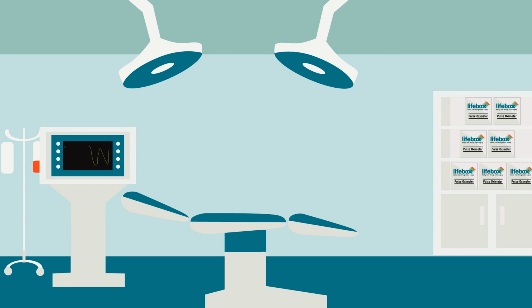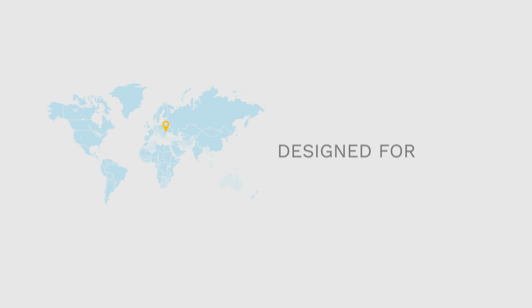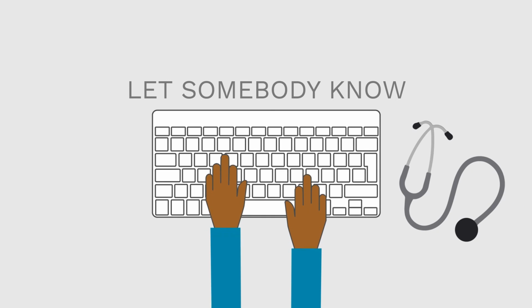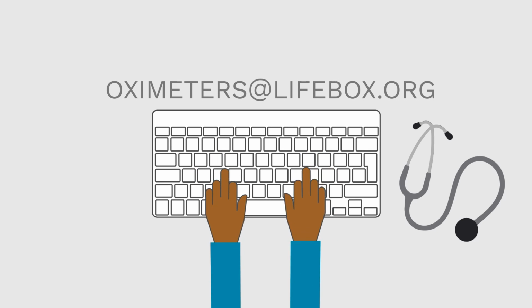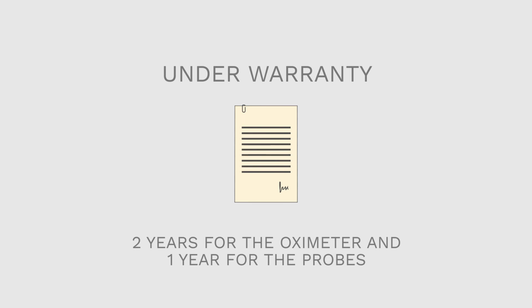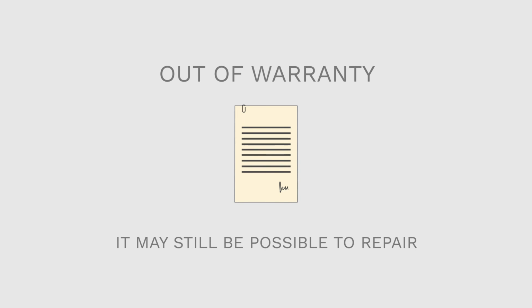Another important point is around maintenance and repair. The Lifebox oximeter was specially designed for challenging environments. It doesn't need calibration, it's easy to clean, and it's robust. But if you have a problem with your oximeter, it's vital that you let somebody know. Do not let your oximeter sit in a cupboard where it can't help you or your patients. The Lifebox oximeter is under warranty, 2 years for the oximeter and 1 year for the probe. If your oximeter is out of warranty, it may still be possible to repair it. Contact information is written on the side of the oximeter.